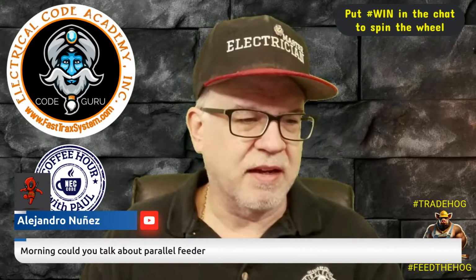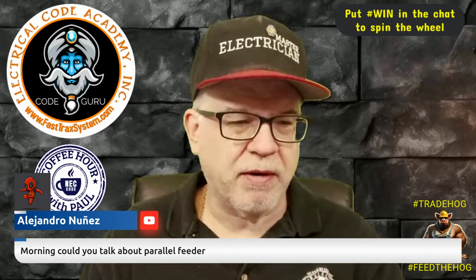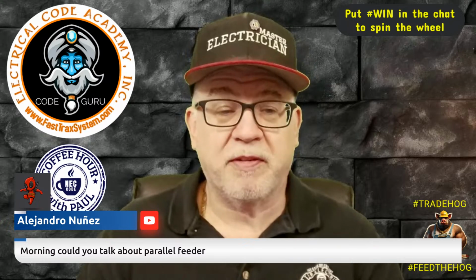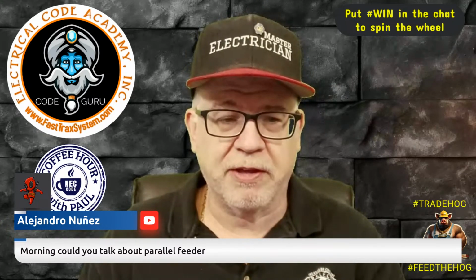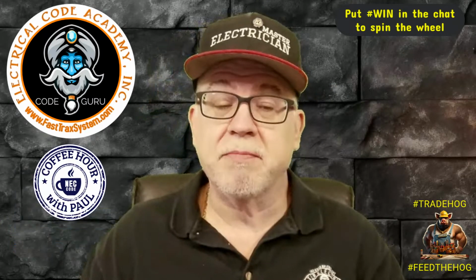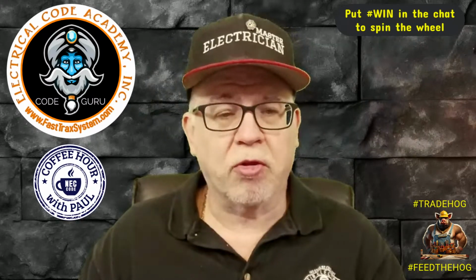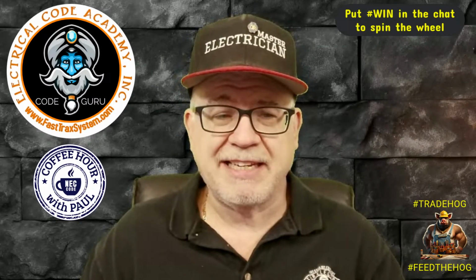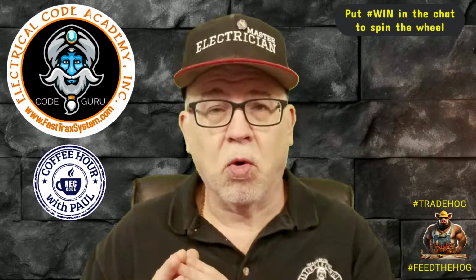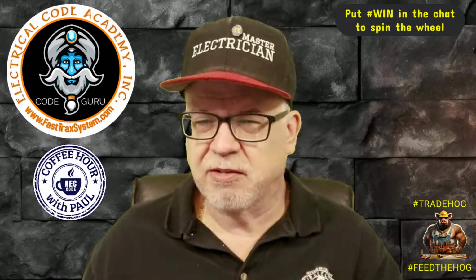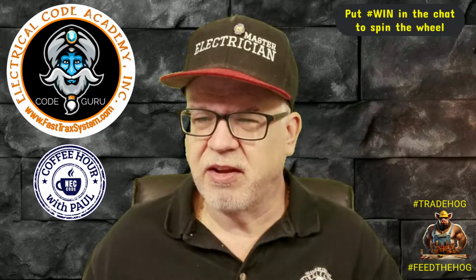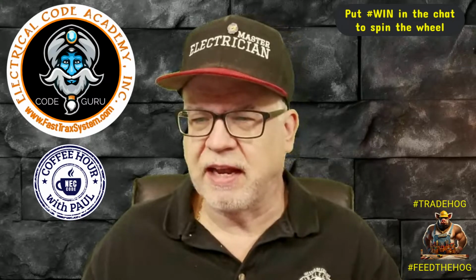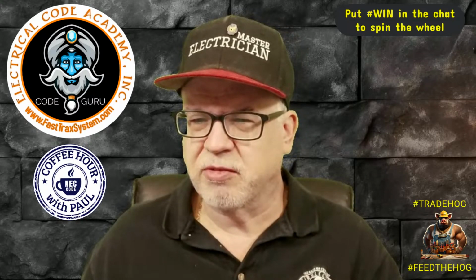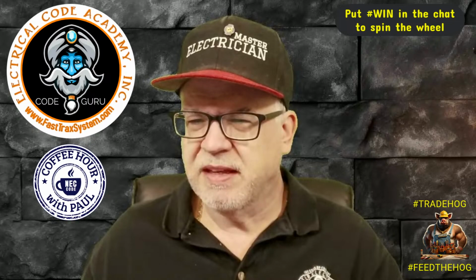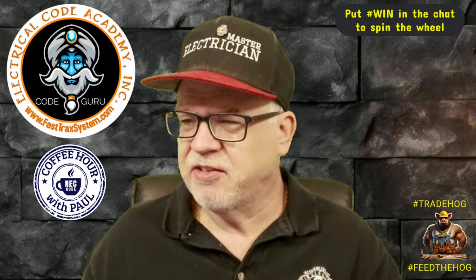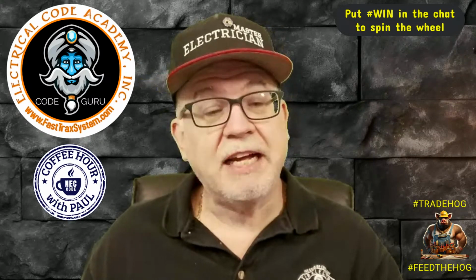Let's see. Alejandro says, could you talk about parallel feeders? Can you be more specific, Alejandro? When you're installing feeders in parallel, you have to follow all of the rules for paralleling in 310.10(H), or I don't know, is it H now with the code cycles? They change, and I have to check it just to see. 310.10. Let's see here. Is it H in the 2023? Is it G? It's G.